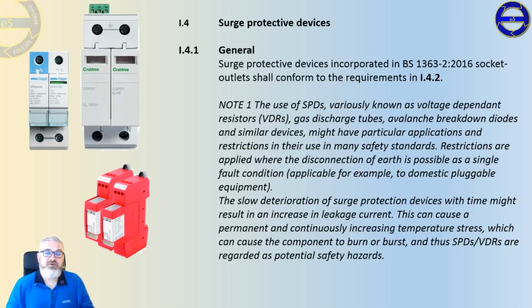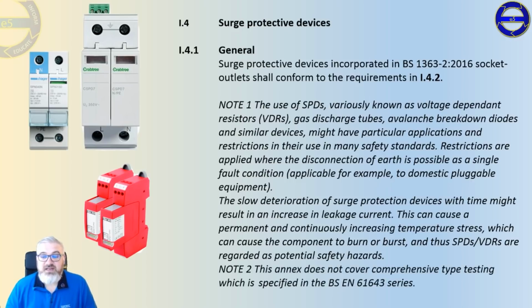Now, I know there are industry bodies who are working on guidance for this new technology, so I would hold fire until these trade associations are actually putting the advice out, giving you the support needed to correctly select and erect surge protection devices. This annex doesn't cover comprehensive type testing, which is specified in another series of standards, BS EN 61643. So electricians know within the annexes there is an annex that just covers standards. Now, over time, when a standard gets improved and the substandards gets improved, not everything makes it into the main body of the standard. Sometimes there are conflicts like this one.